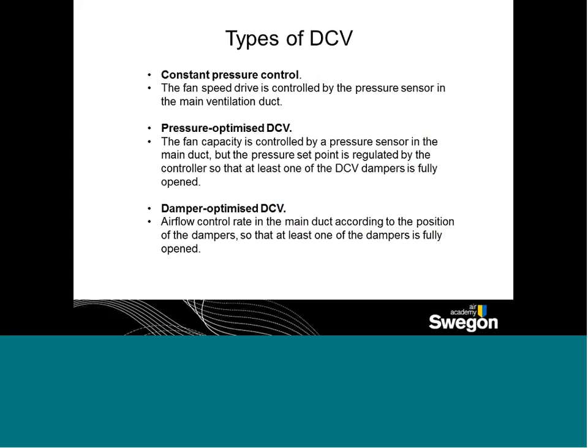There are at least three different types of DCV system, and you want to pick the one that fits the building you're considering. First is constant pressure control, where the fan is driven or controlled through a pressure sensor in the main ventilation duct at a suitable distance away. Then there is pressure-optimized demand control ventilation, where you have a pressure set point regulated by the controller so that at least one damper is fully open. The optimal today is damper-optimized DCV, where you're always making sure at least one damper is fully open. It's important to consider which type of DCV system best characterizes your application.